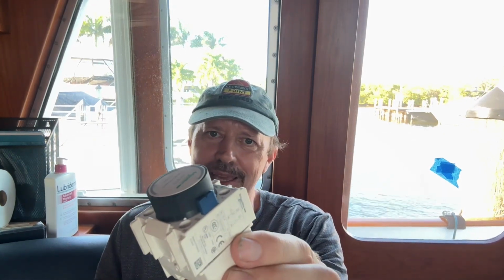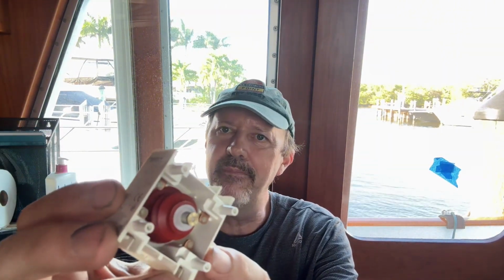So coming from a software world, you might use a sleep or an async await type thing to do delays. But in the mechanical world, how do you do such a delay? It turns out you use a purely mechanical device that uses an air vacuum to control the delay. This is a delay timer that sits on top of a contactor, or a relay basically. And I've unscrewed it so you can open it up. And in here you see a little air diaphragm.